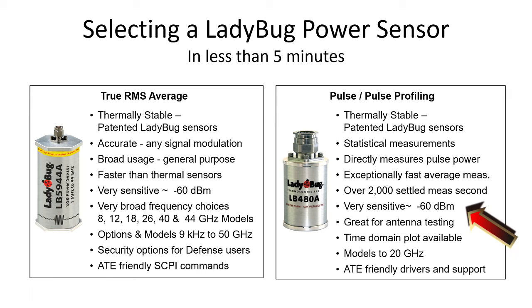The measurements for this sensor are exceptionally fast, 2,000 settled measurements per second at full sensitivity, minus 60 dBm. It makes it great for antenna testing and other source testing where you have a CW signal and you just want to get a quick calibration point. Works very well for that. The pulse profiling software adds a time domain plot.